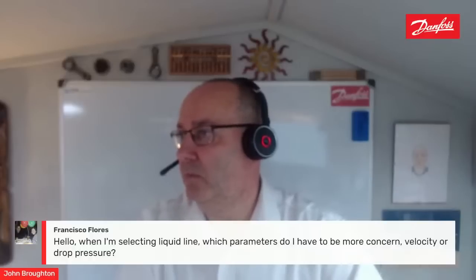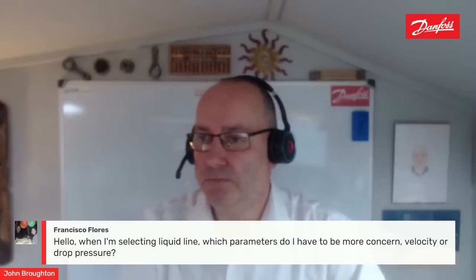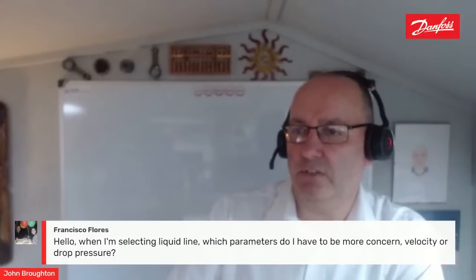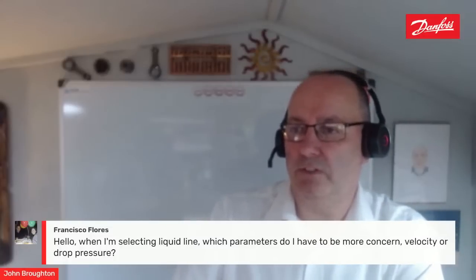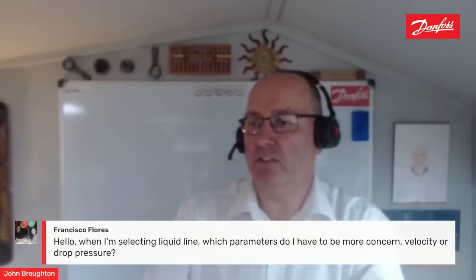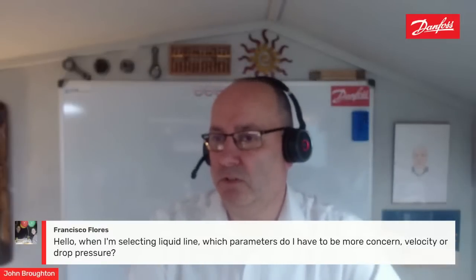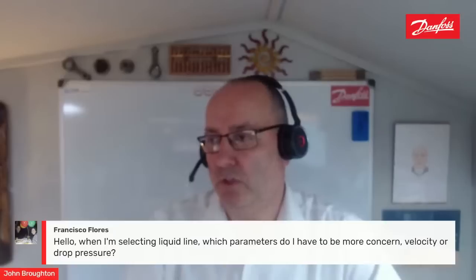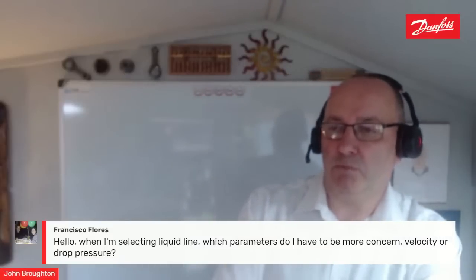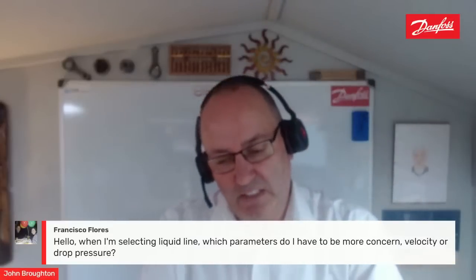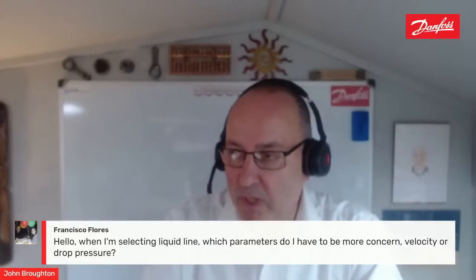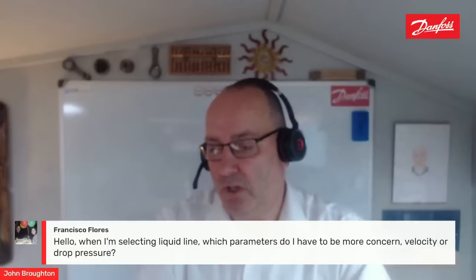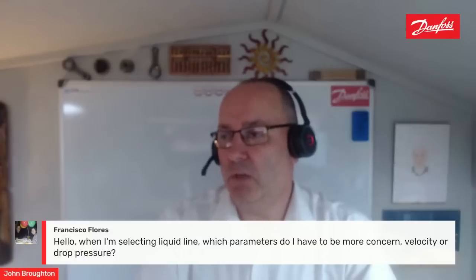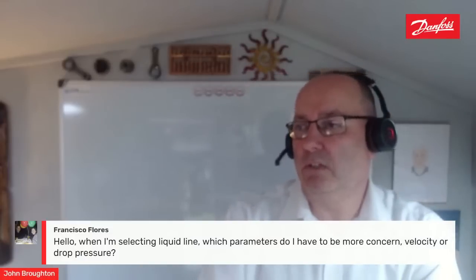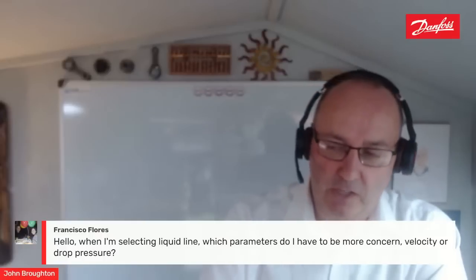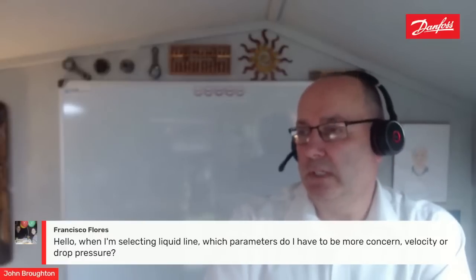There's a question from Francisco. Francisco says, hello, when I'm selecting a liquid line, which parameters do I have to be more concerned with, velocity or pressure drop? For me, velocity, because pressure drop in a liquid line is not a big concern. Pressure drop in a suction line is a big concern, but velocity, keep your velocity around 1 meter a second, and everything will be fine. If it's higher than that, you can have some noise.